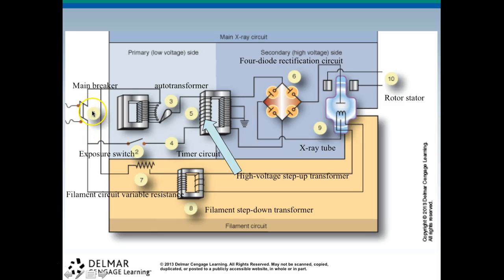So 1 is your main breaker, 2 is your exposure switch, 3 is your autotransformer, 4 is your timer circuit, 5 is your high voltage step-up transformer. 6 is your 4 diodes. There's 4 of them, the rectification circuit. 7 down here is your filament circuit variable resistance. And 8 is your filament step-down transformer. 9 is your X-ray tube. And 10 is your rotor stator right here. That's the electromagnetic induction spinning your anode.